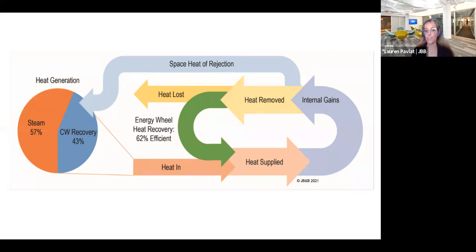Then on top, the space heat rejection line shows that 43% of our heat generation from condenser water recovery reduces heat generation to only 57% steam. So we were able to almost halve our heat generated through recycling. This diagram really shows how impactful this design is.